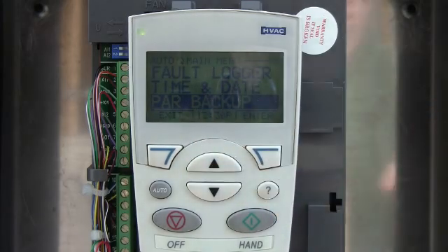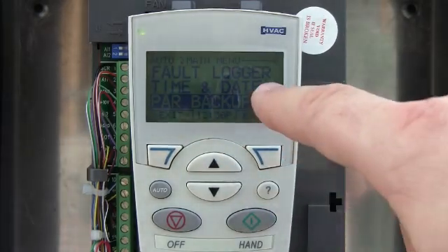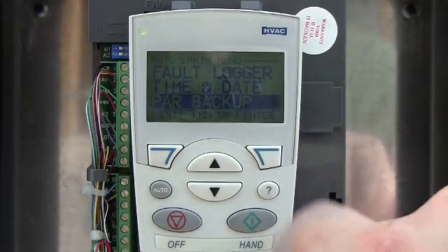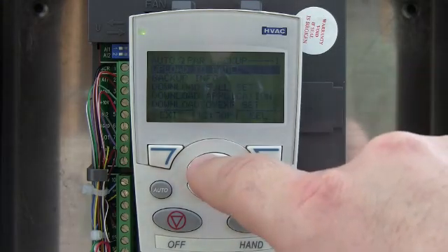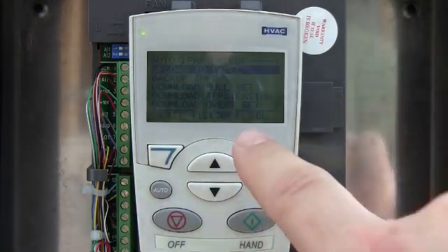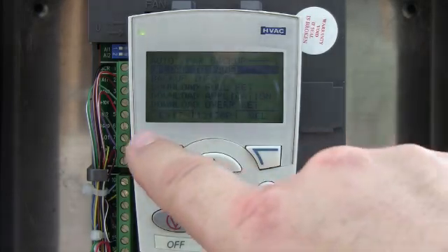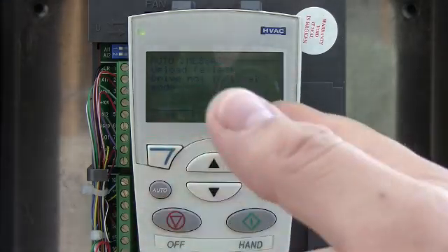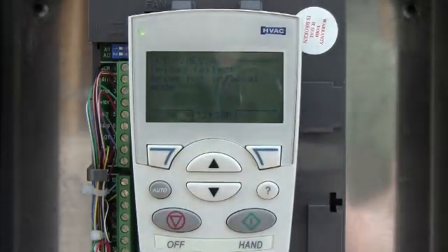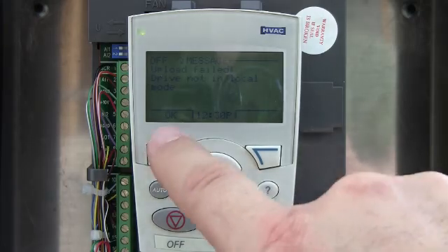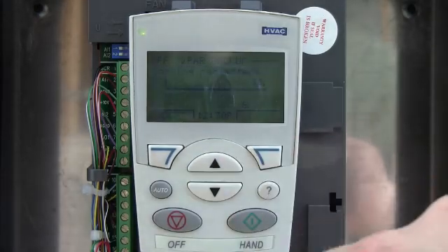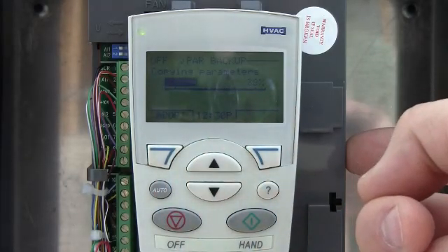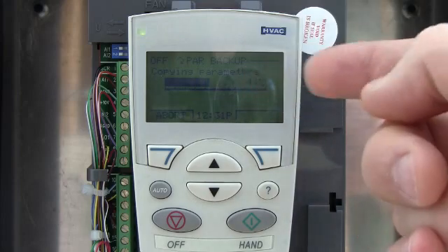Parameter backup is very handy. This is basically for when you're finished starting the drive or programming it and you want to make a backup. If you enter into that, you have a couple of different selections. If it hasn't ever been touched, all it will have is upload to panel. If you hit select or SEL, it'll say copy. I got a failure because I have it in auto mode, so I'll push off, push OK, upload — and you'll see this bar. It's taking the program off the main control board and dumping it into the keypad.